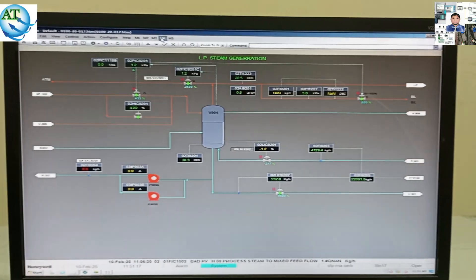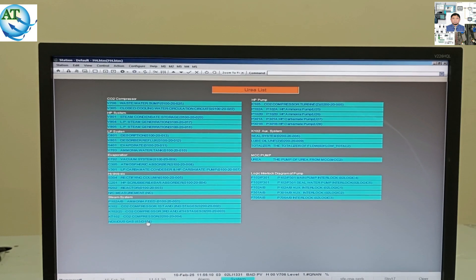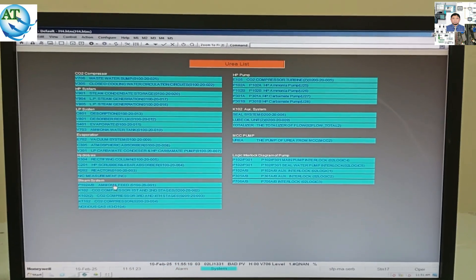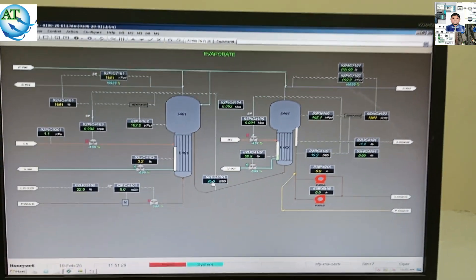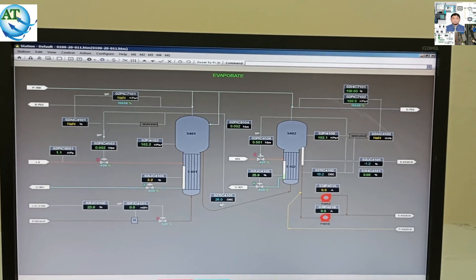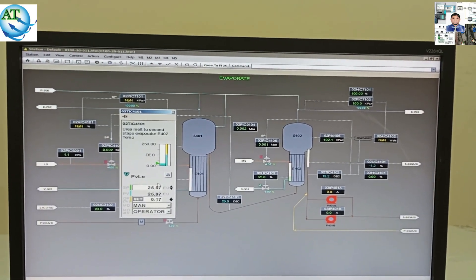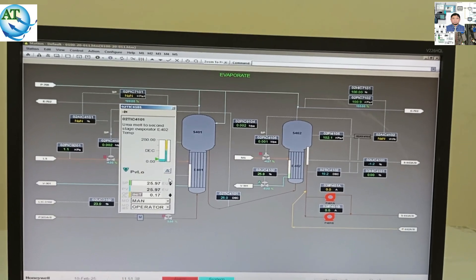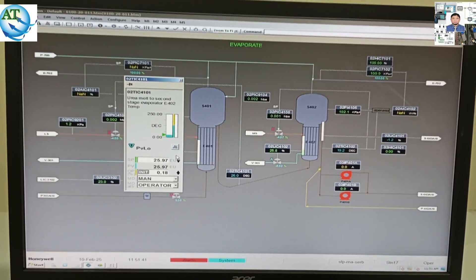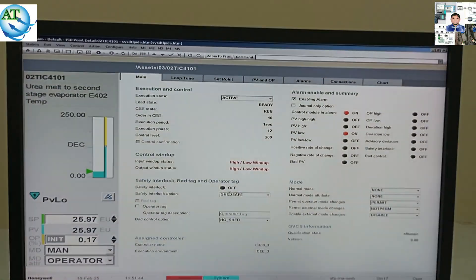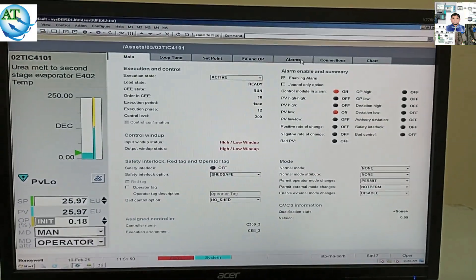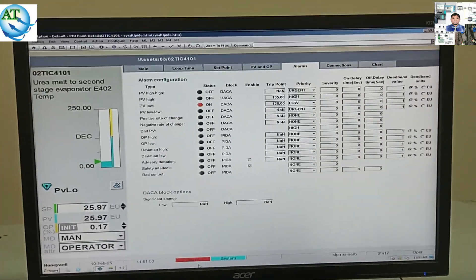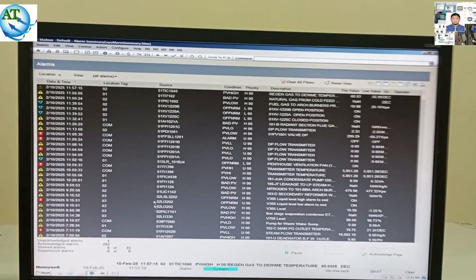You see, this is our plant Honeywell page. Here, for one of the tags I want to change the alarm priority. When the alarm is coming it is only a low sound, but I want to get a higher sound or the chirp sound. Our desired tag number is 02 TIC4101. This tag alarm is already configured, and I want to change only the priority number. You can see here the PV high and PV low — two types of alarm settings are available.